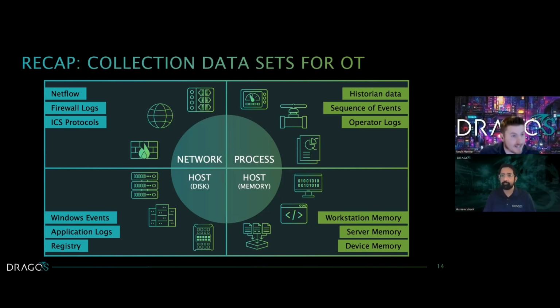Understanding the process is key when performing OT incident response, because you want to understand that series of events, maybe that open and close valve, that upload logic, download logic, anything you can get from the historian, because it is pretty much the recorder of all events in the environment. And most importantly, those operator logs. Understanding the initial symptoms of the events, when the operator raises their hand and says there's something wrong here, or maybe there's a change in set points that wasn't authorized, and the operator records it in their logs. These are excellent resources in the OT environment to gather and consider when developing your plan going forward.